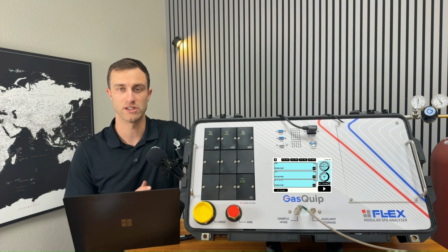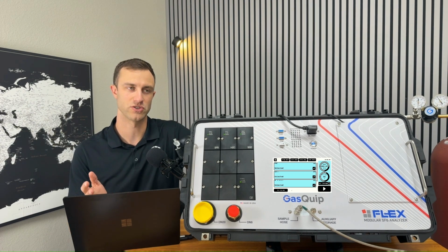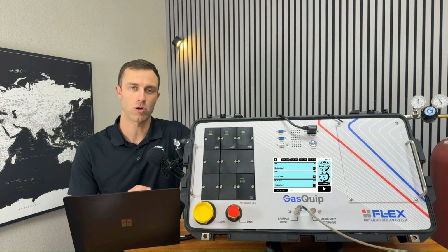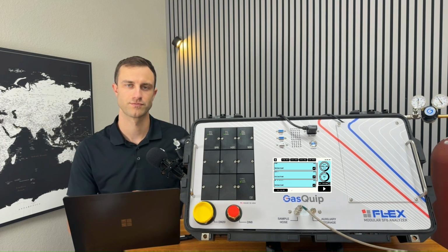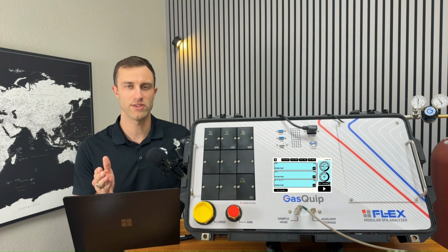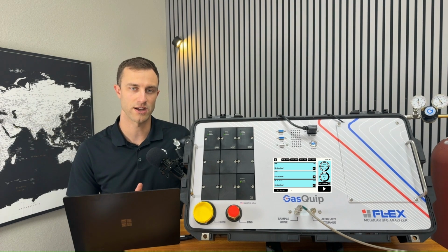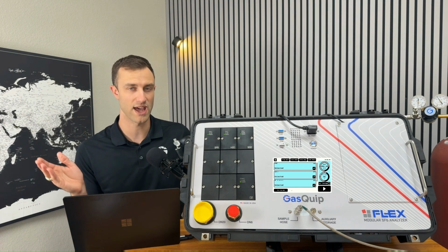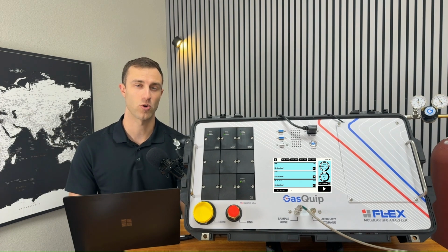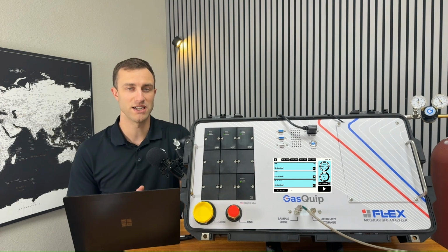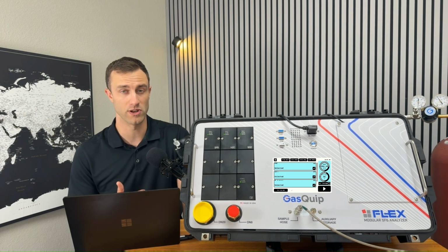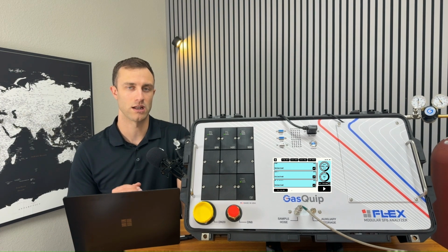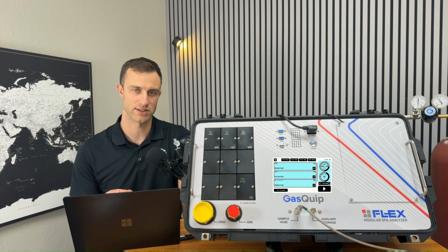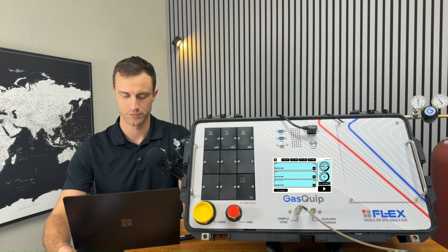You want to run that dry system function if you've had your analyzer sitting out on the shelf for a long time and you haven't had dry gas running through it for a while, or also if the tests you're getting are showing a much higher moisture reading than you would have anticipated. That can also help lower the results down to the dryness you would have otherwise anticipated. And that'll run for about 5 minutes.